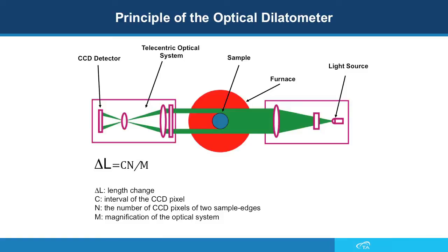The light emitted from the source goes through a diffusion unit and a lens that produces a uniform short wavelength plane of light. The sample blocks the light and the shadowed light goes through a telecentric optical system. The width of the shadow is detected by the edge detector. The change in length is calculated by multiplying the interval of the CCD pixel by the number of CCD pixels of the two sample edges, dividing it by the magnification of the optical system.